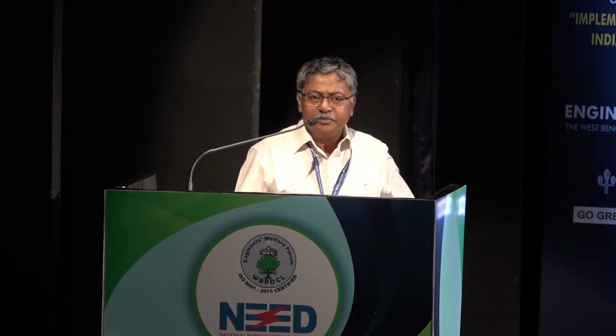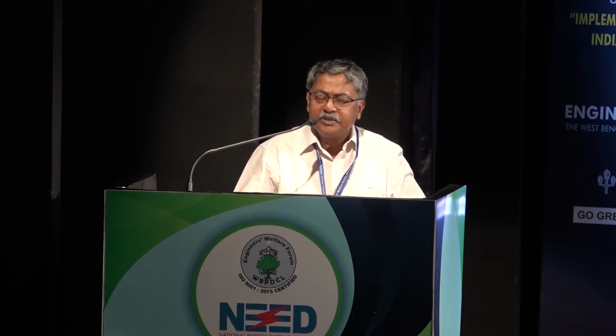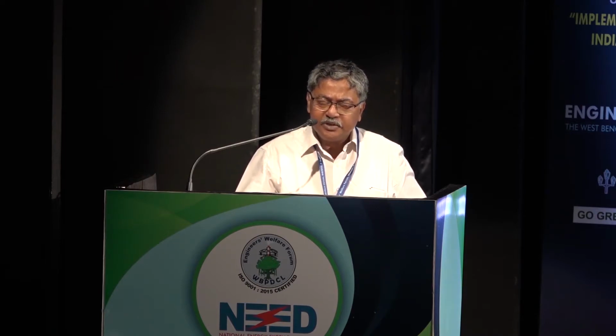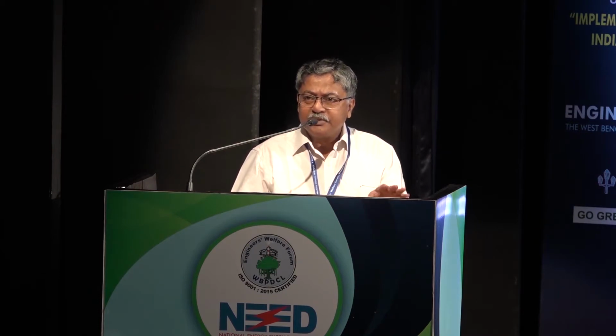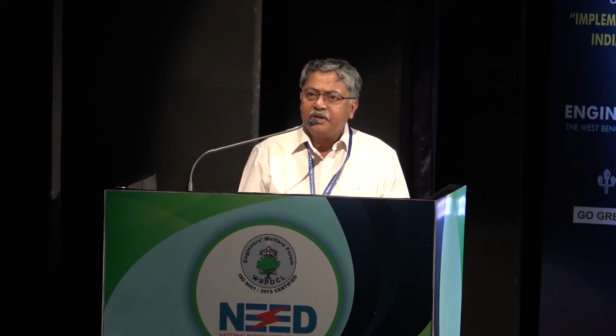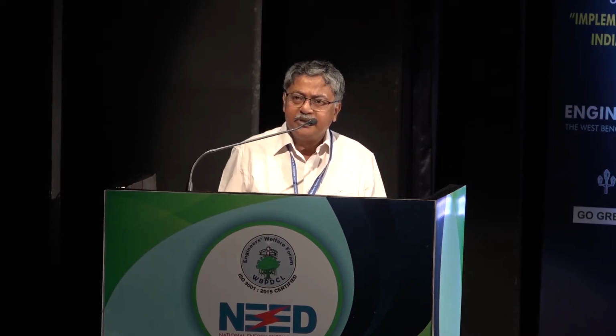So very crucial is how do you grind, how do you pulverize that limestone, because entire efficiency of the process depends on the desired fineness. This word is very important, desired fineness of limestone. Desired in the sense its size must be such that large surfaces of particles are available for reactions. Large surface areas. You can get large surface area only when you have very fine size particles. More the number of particles, larger is the surface area.